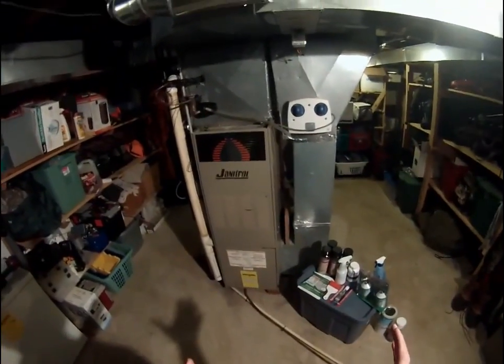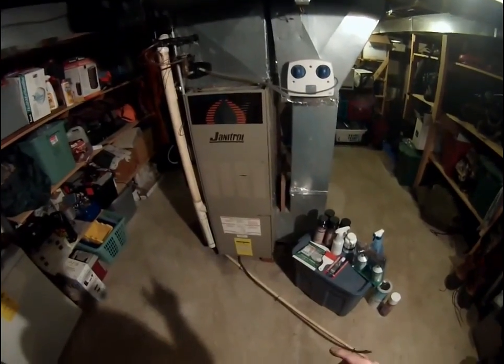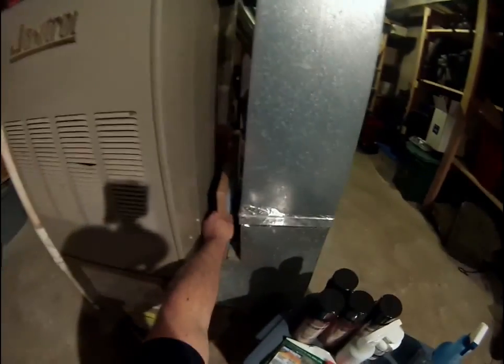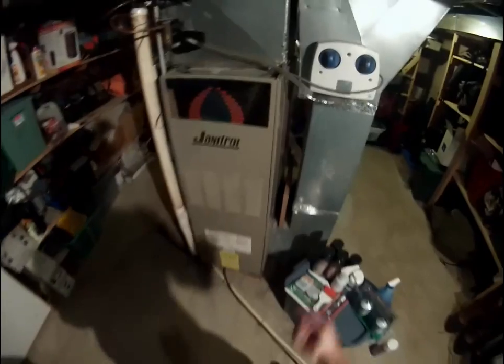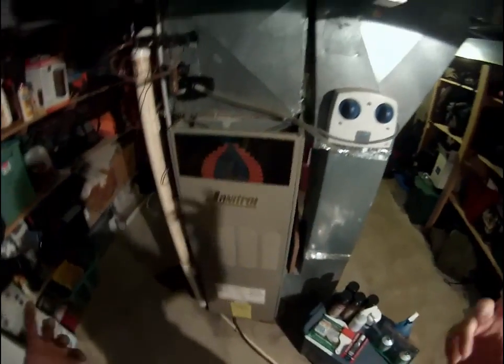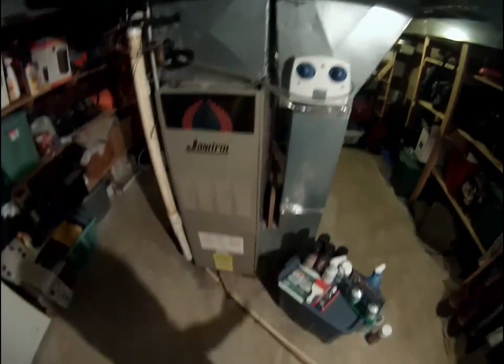So the first section we'll focus on is the airflow issue. First and foremost is your air filter, and they can be anywhere from in the ductwork to down in the cabinet of your furnace, up in a grill, up in the ceiling. Sometimes they're up in an attic. So you want to check that and make sure that that's not restricted.